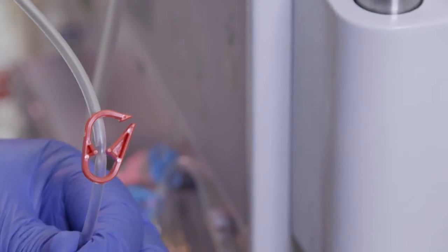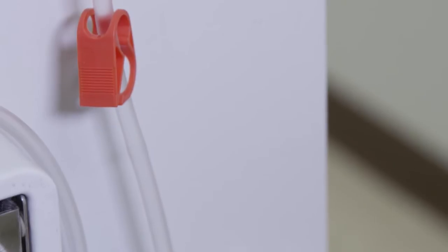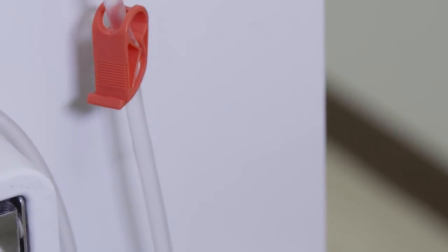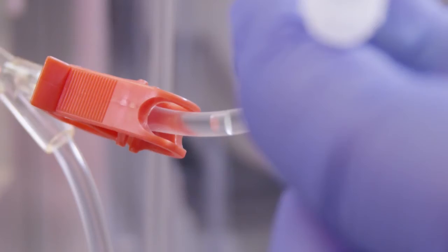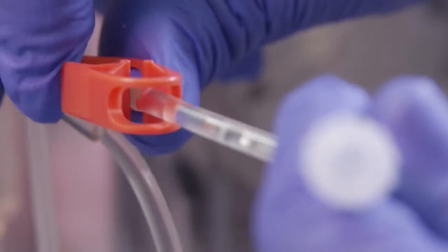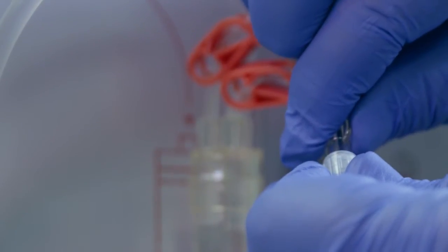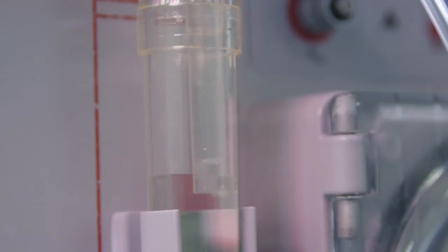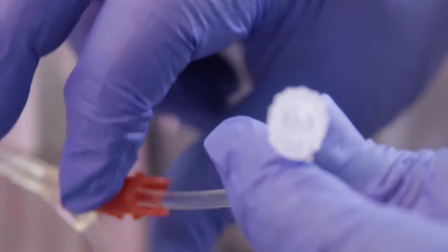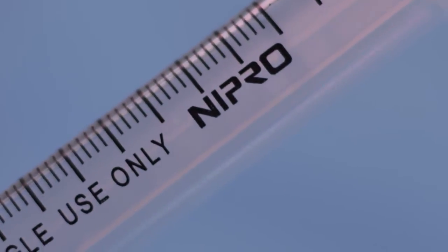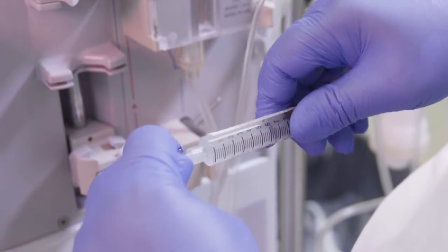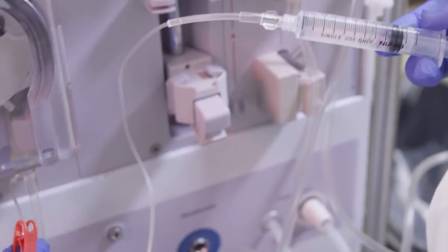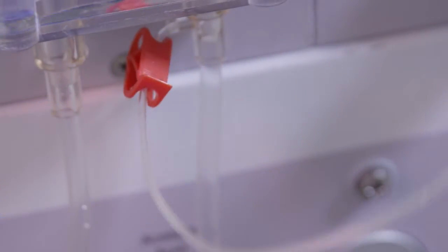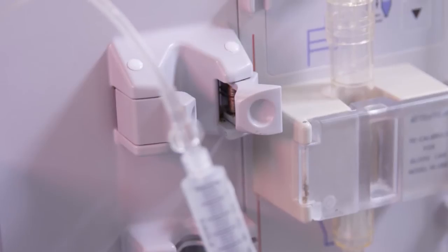Open the saline clamp and prime the arterial line. Close the clamp once air is purged from the patient end of the arterial line. Open the short infusion line clamp on the arterial drip chamber and loosen the cap to allow the arterial drip chamber to fill 3/4 full. Then tighten the cap and reclamp the line. Attach a maintenance heparin syringe and prime the heparin line. Reclamp the heparin line as close to the arterial blood line as possible. And secure the heparin syringe in the holder.